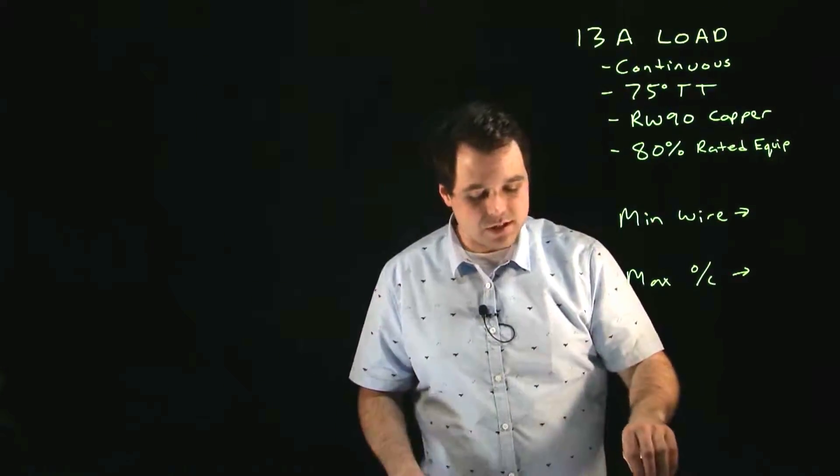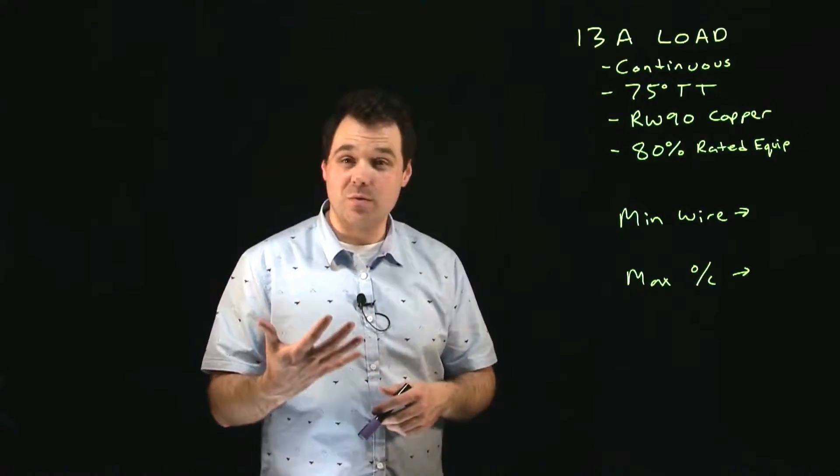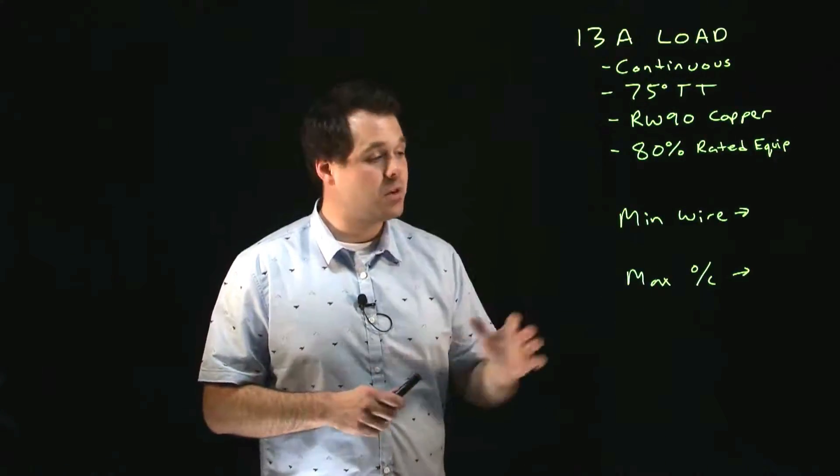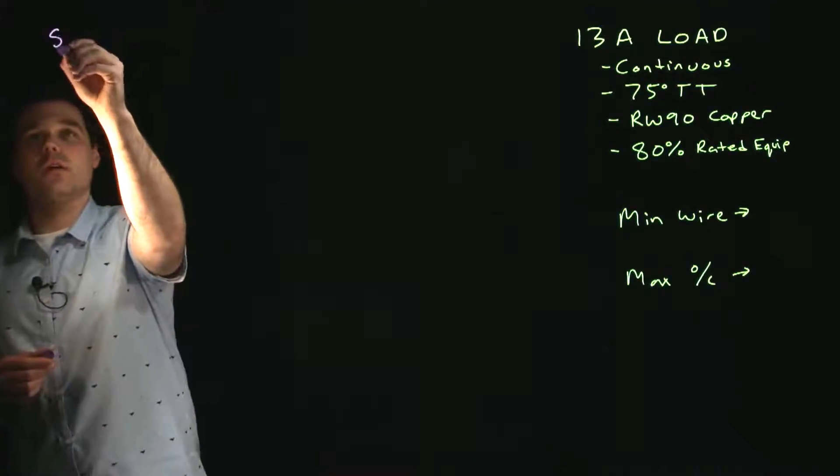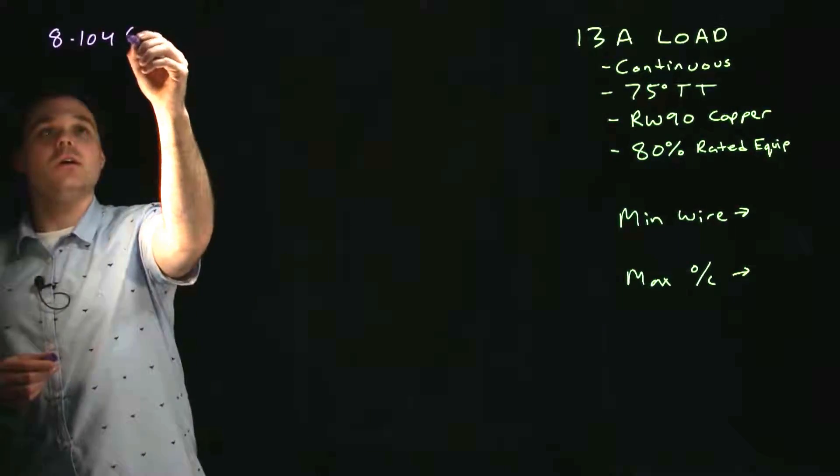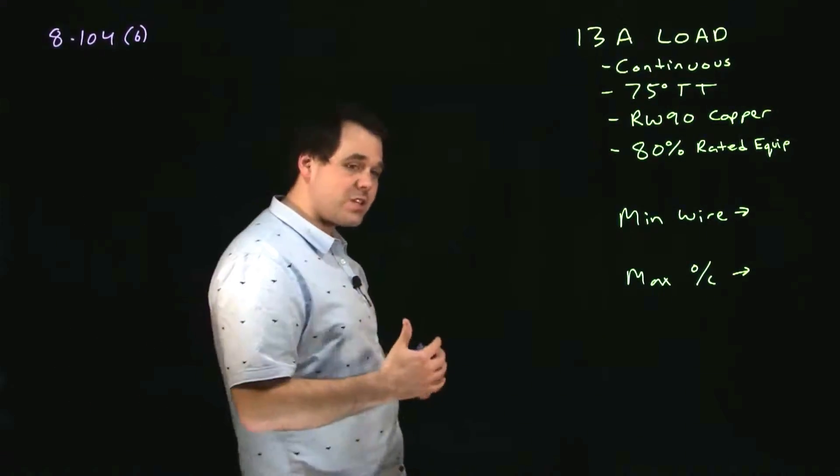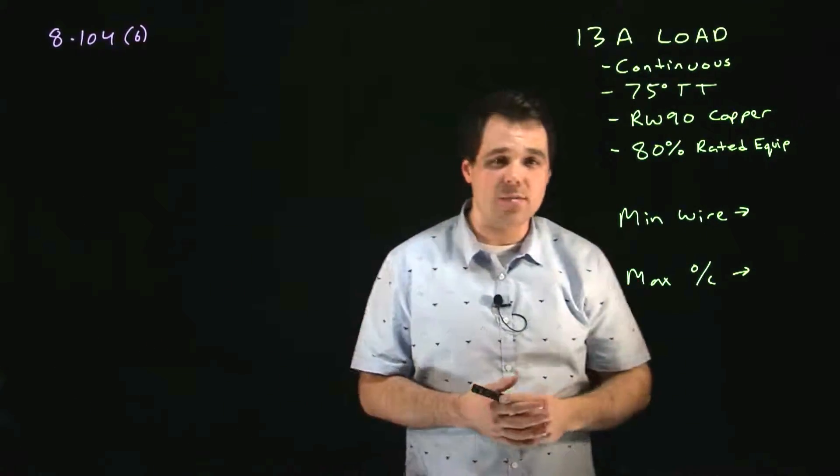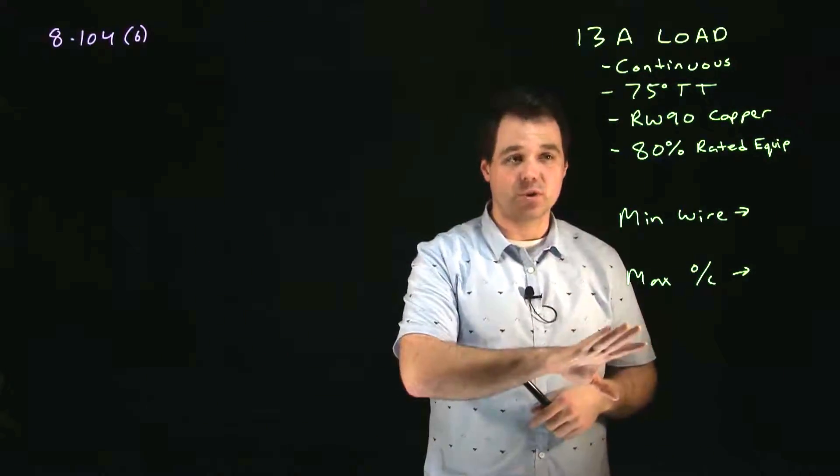So because this is a continuous load we are going to be referencing section 8 circuit loading 8-104. Specifically because we're using 80 percent rated equipment we are going to be using 8-104 sub rule 6. Now 8-104 sub rule 6 is where you're using 80 percent rated equipment. Your load cannot exceed 80 percent the rating of the circuit breaker.